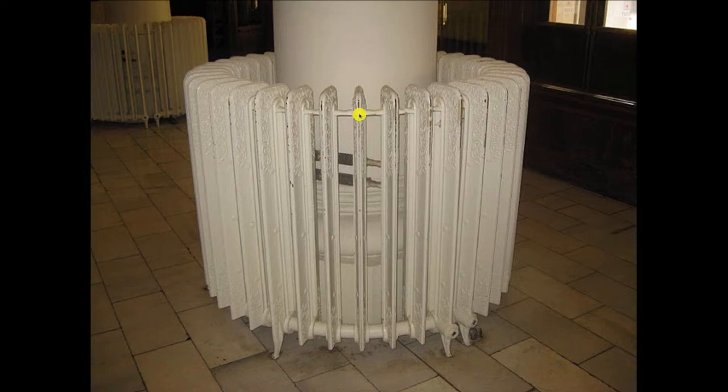There's no nipples on the top — nipples only across the bottom. We've got two sections. The steam goes into here and steam also goes over to here. And we've got these nipples that are angled. Could you do this? Could you put this together? There's not a union anywhere in this thing.